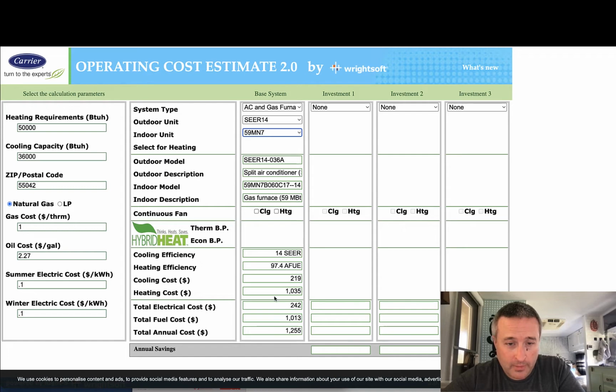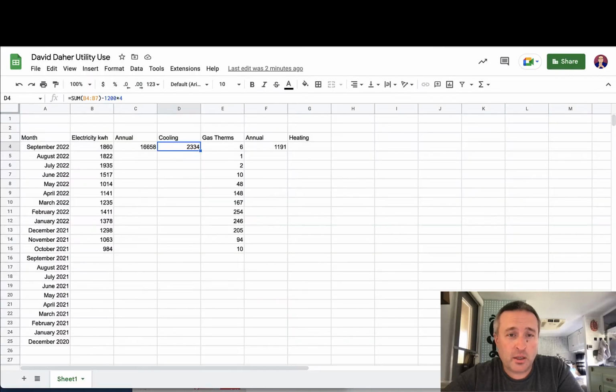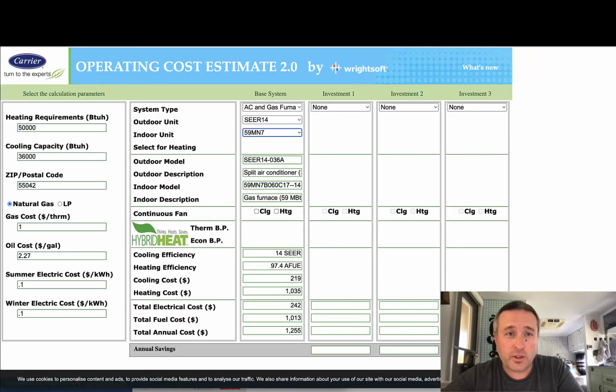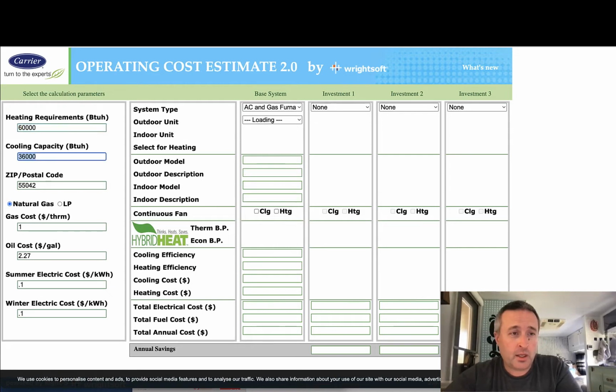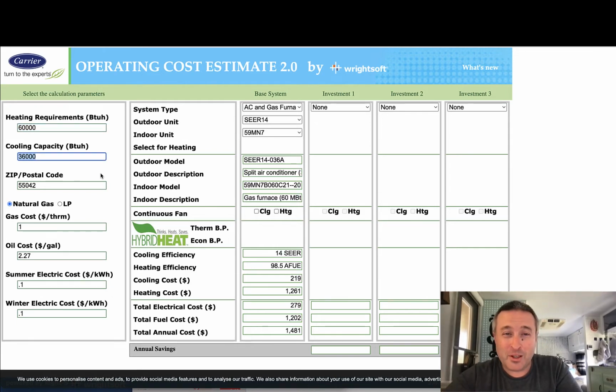Let's see here - total fuel cost. At 50,000 heat load he's at 1,013, and we're trying to get to 1,200, so it's going to be more like 60,000. Keep in mind this is a very low design temperature, below 0 Fahrenheit, which is not super common.